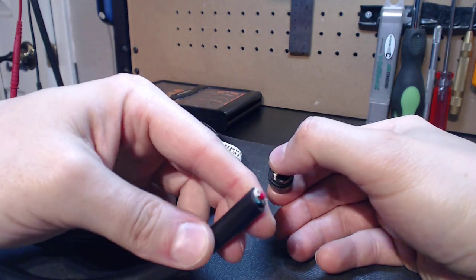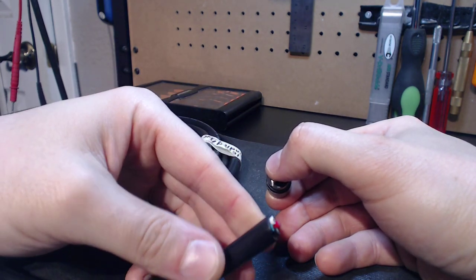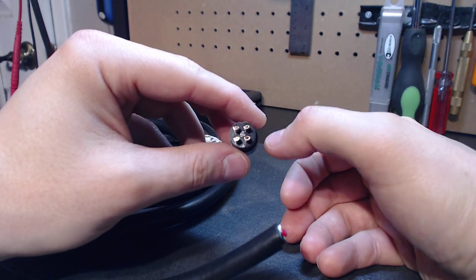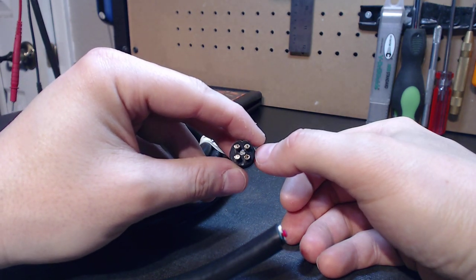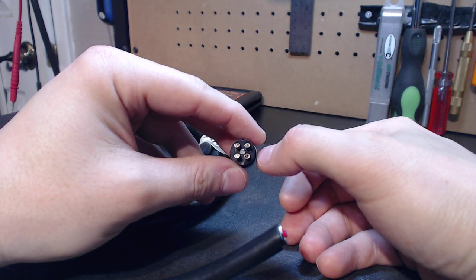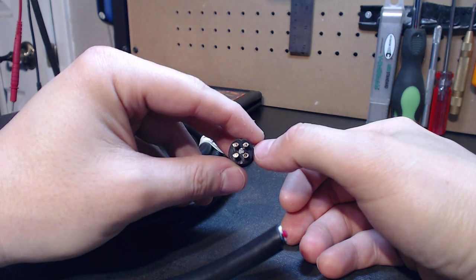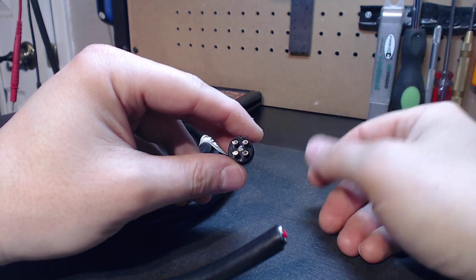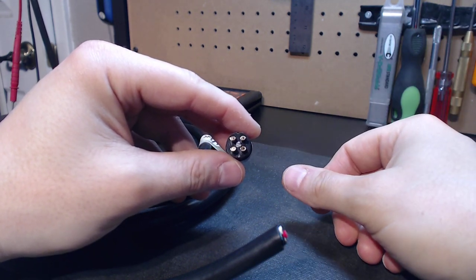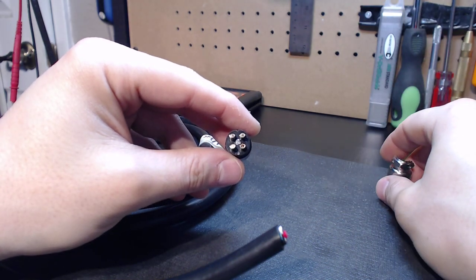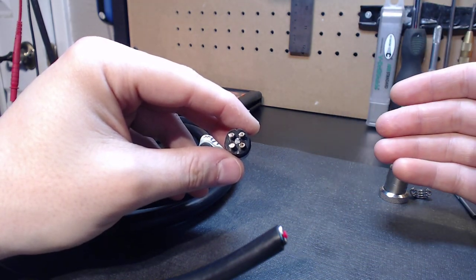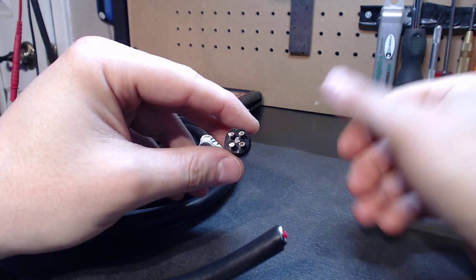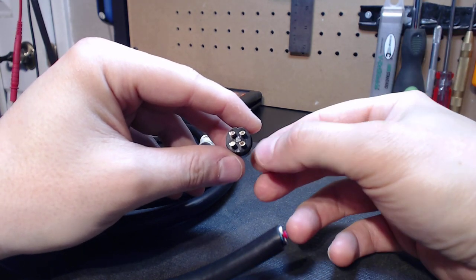You want to make sure that that solder is not only adhering, but it's properly bonded in the sense that that flux is actually cleaning these terminals for the proper connection. We've already covered the terminal placement. Pins one, two, and three can be any color lead other than green, which green will always be ground. Ground will always go to pin four.